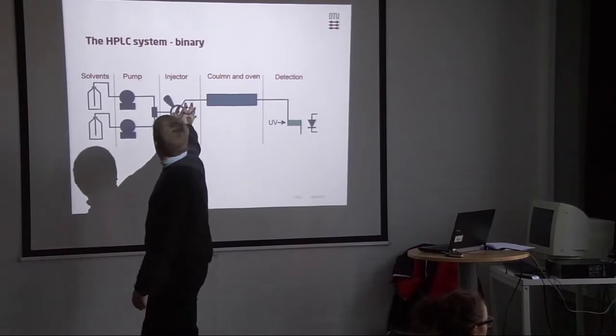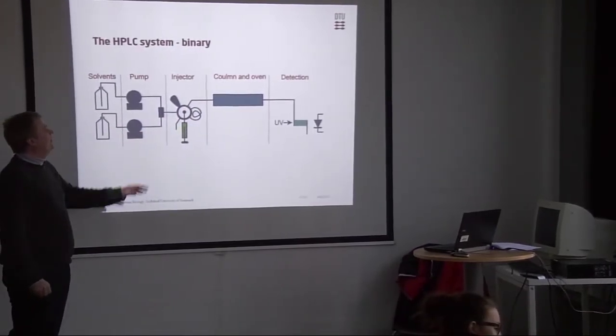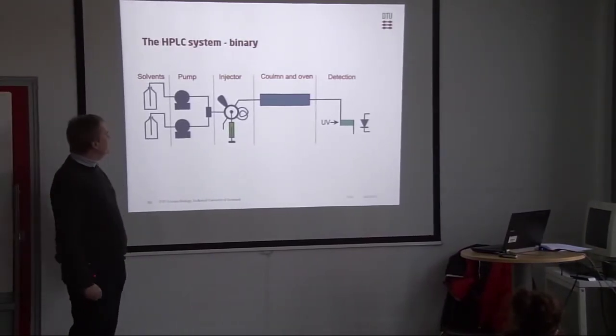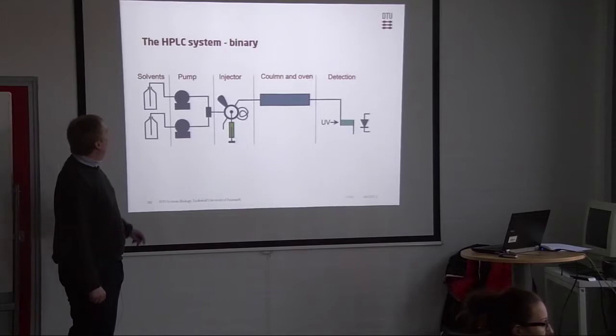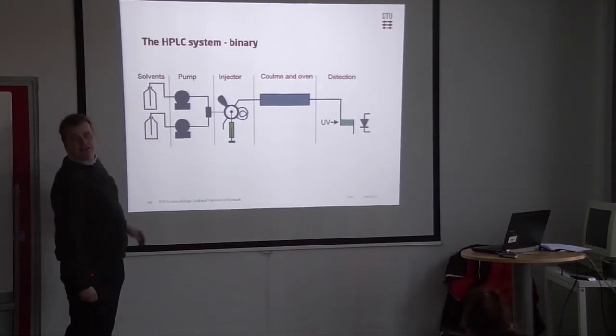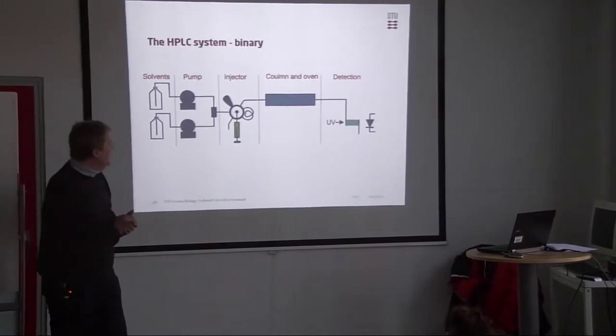This is also why we need to filter the samples, because it also kind of clog up all these tubings. So the heart, the column, sits in a thermostat, so we know exactly which temperature it has. We have to inject our sample, and we have our pumps and our solvents, and then we have to go to our detector. This is more or less an HPLC system. And if you want to add a little more, you could say we actually have a degasser here, or we have to degas our solvents.